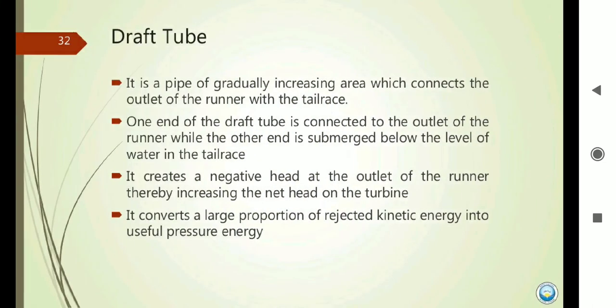The draft tube is a very important part. It is a simple tube with a gradually increasing area — fitted at the exit of the turbine. The area at the entry of the draft tube is small and at the exit is very large. This maintains a pressure difference. Without the draft tube, the exit pressure of the turbine is low and atmospheric pressure is high, causing water to flow in the opposite direction, creating a low pressure area. When the pressure drops below the vapor pressure, the cavitation effect forms, which is harmful to the hydraulic turbine. To prevent this, the draft tube creates a negative head at the runner exit, thereby increasing the net head of the turbine and converting the kinetic energy of the exiting water into useful pressure energy.